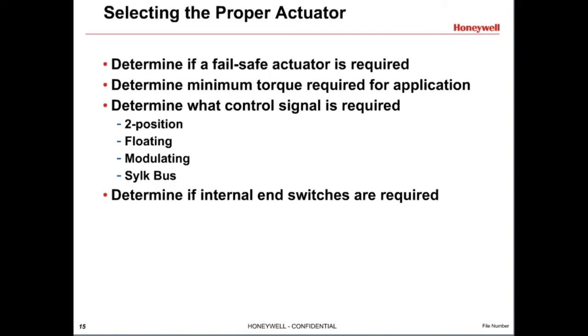Proportional control uses a voltage or current to set the location that the actuator will drive to. For example, if a 0 to 10 volt control signal is used, then 0 volts will signal the actuator to be fully closed. A 10 volt signal will tell the actuator to drive fully open, and a 5 volt signal will tell the actuator to drive 50% open.